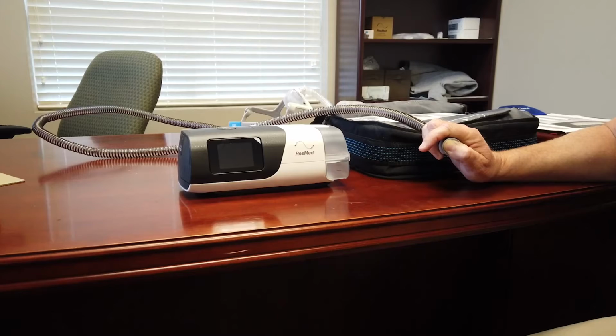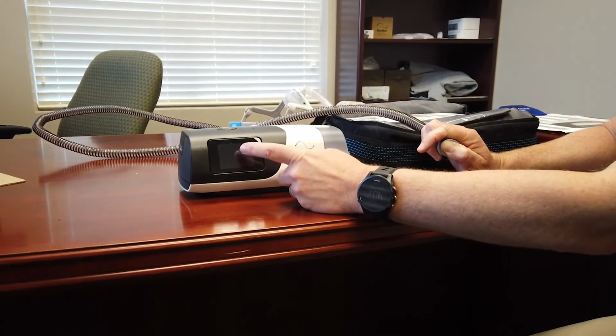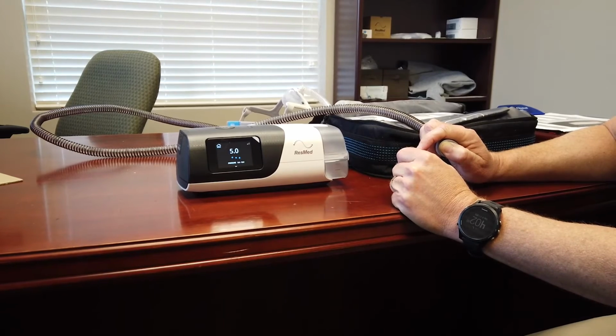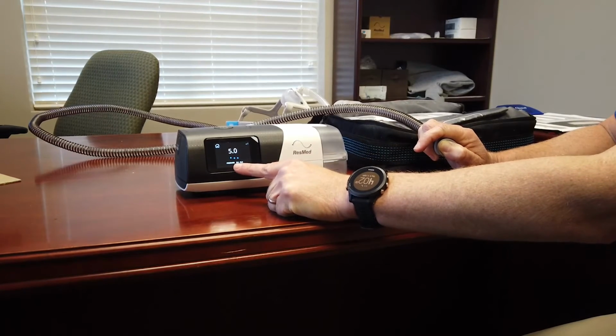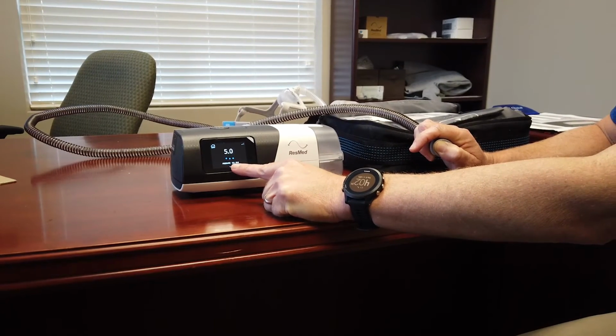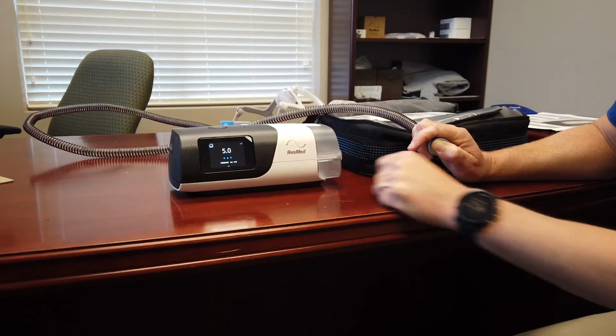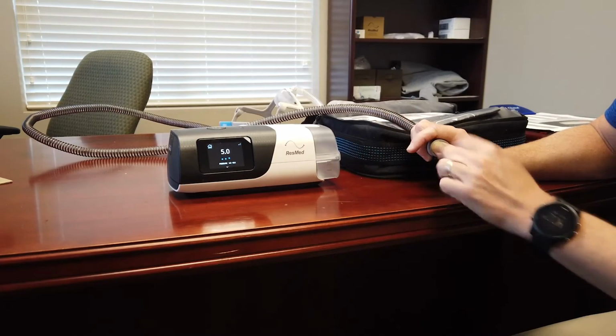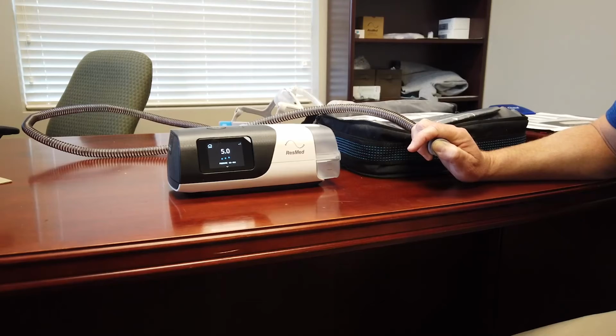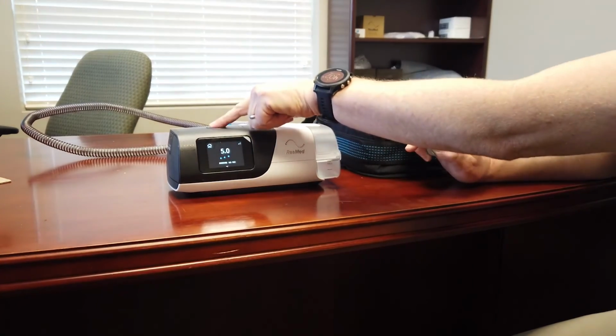As you see, the screen goes dark pretty quickly, and that's just so that it's not lighting up the room while you're asleep. That's why I keep having to touch this touch screen to turn it back on. Your actual CPAP machine settings will show up right here. So this one is set from 5 as the minimum, 15 as the max. So that's the range that it's going to work within. So that will show you your settings. So I'm just going to go ahead and cut it back off with the button on top here.